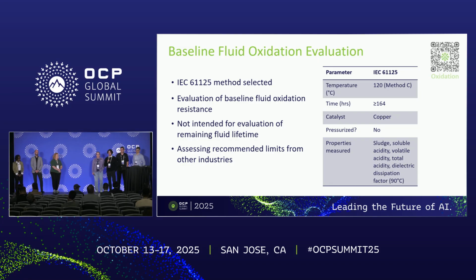As I mentioned, we're looking at using IEC 61125. We're using this as a baseline fluid oxidation evaluation, meaning that it's really to evaluate initially a fluid's tendency to oxidize. We're not intending it to be a test that you use to evaluate the remaining lifetime of your fluid. It's more just to make sure that any fluids entering the OCP marketplace are going to meet the standards and meet the timeline that we need for these fluids to last in service. Currently, we've settled on this method. We're assessing some of the recommended limits from other industries like transformer oils, but keeping in mind that the immersion use case will be slightly different.